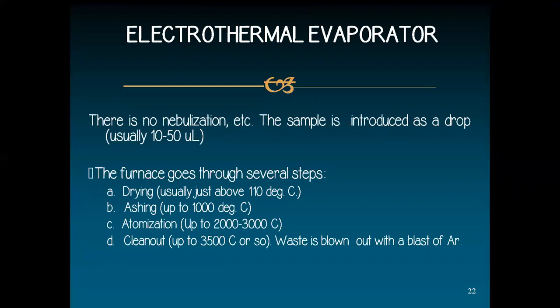Now if you use these electrothermal evaporators, then definitely we won't require nebulization, etc. So the sample is introduced as a drop in the electrothermal evaporator. Electrothermal evaporator means with the help of electricity we will cause evaporation there through heat. So usually we can use samples as low as 10 to 50 microliters, which are introduced as a drop on the evaporator, and it contains a furnace sort of thing.